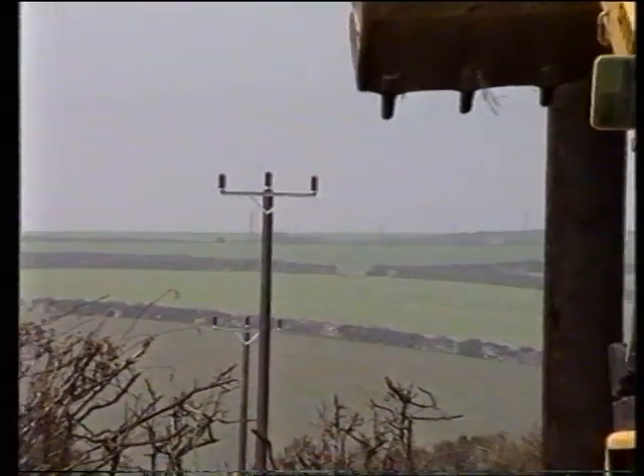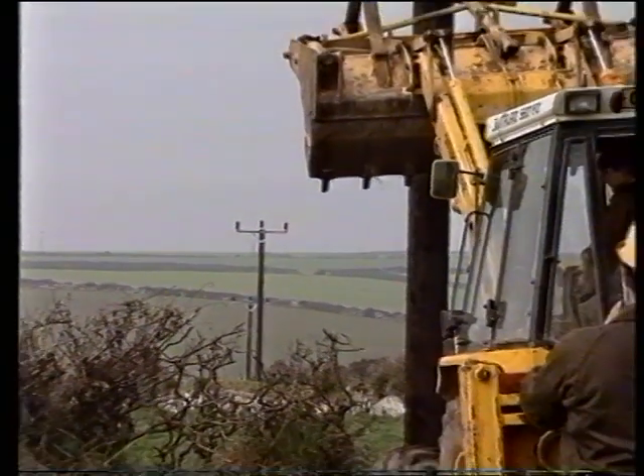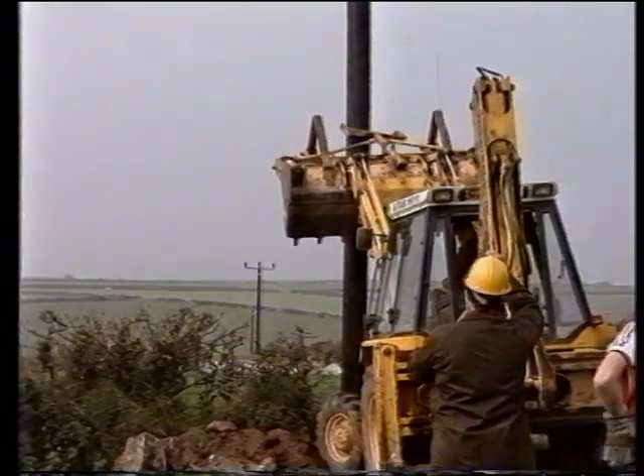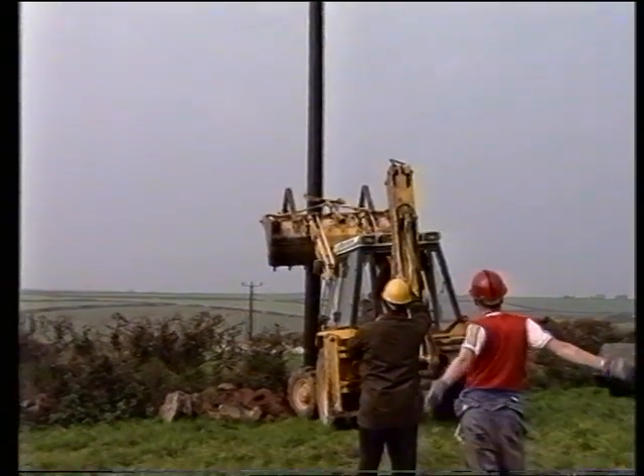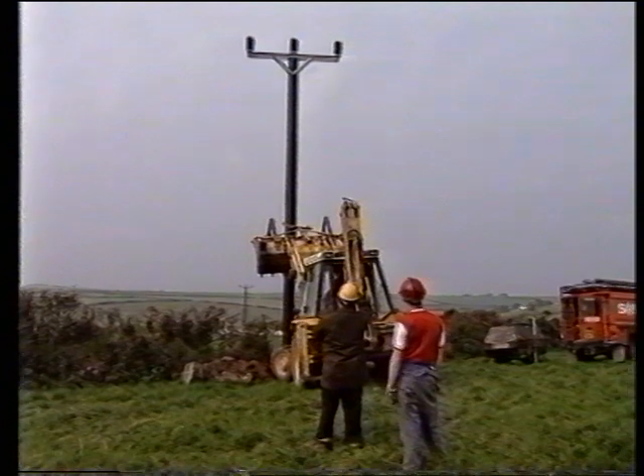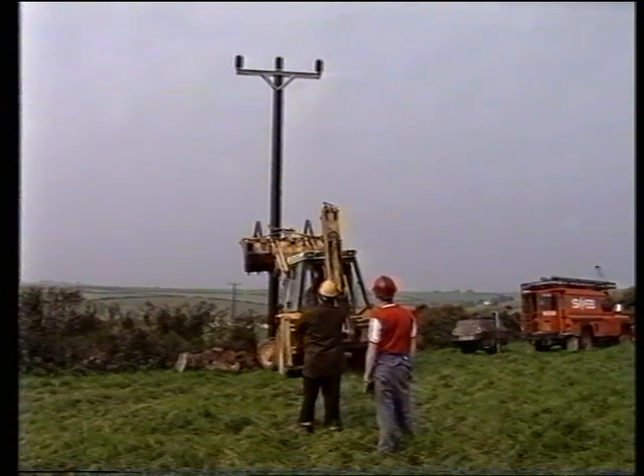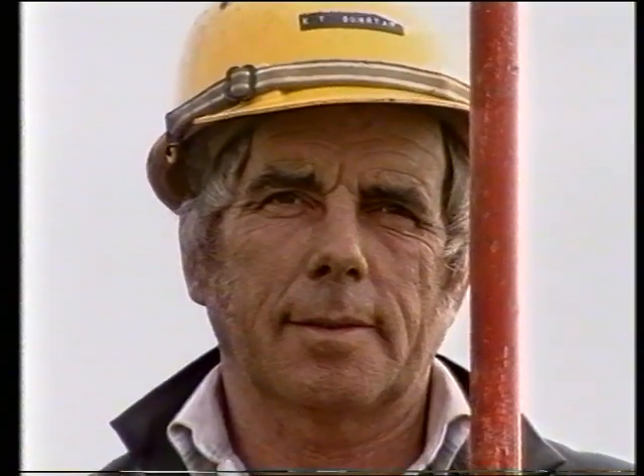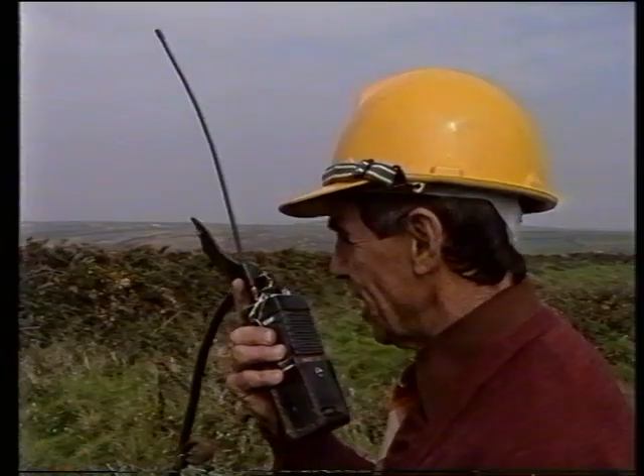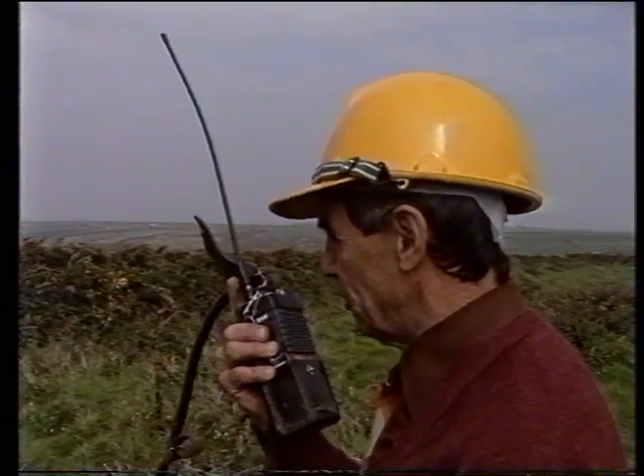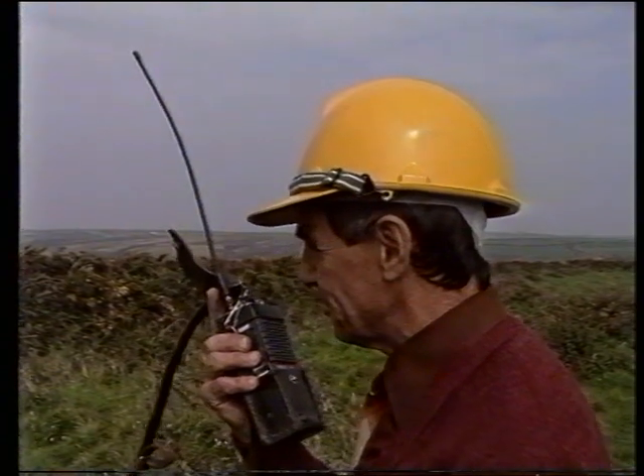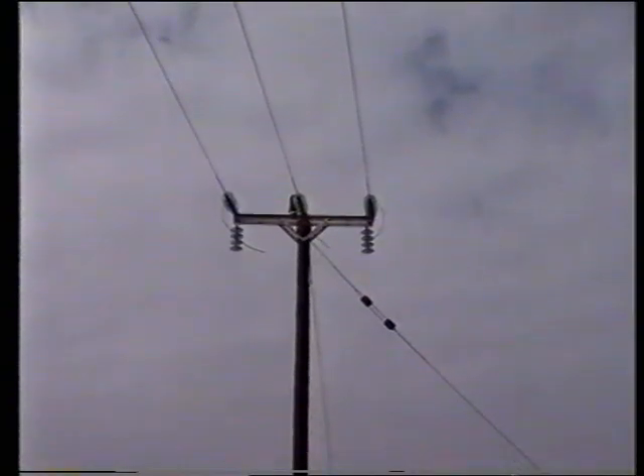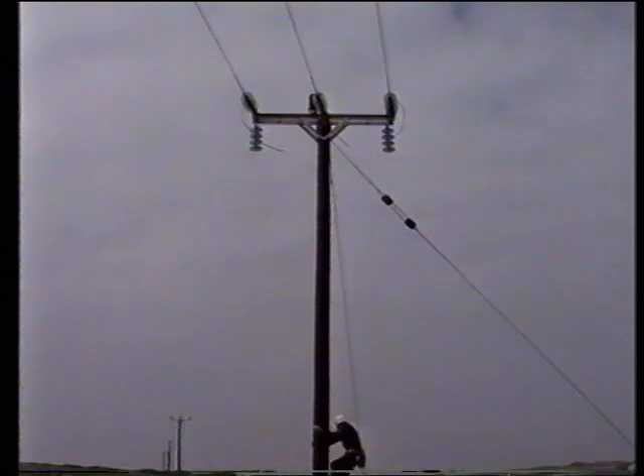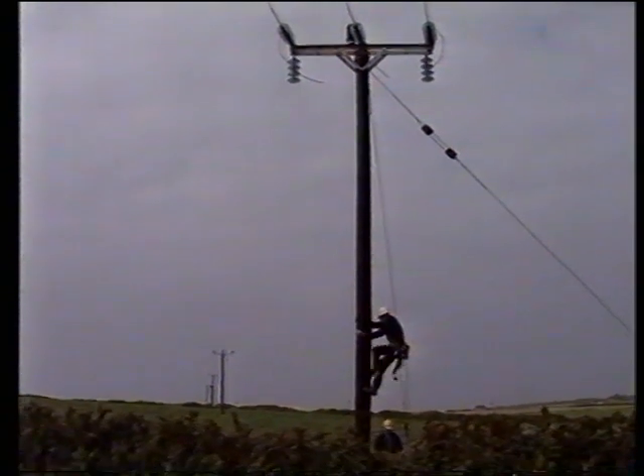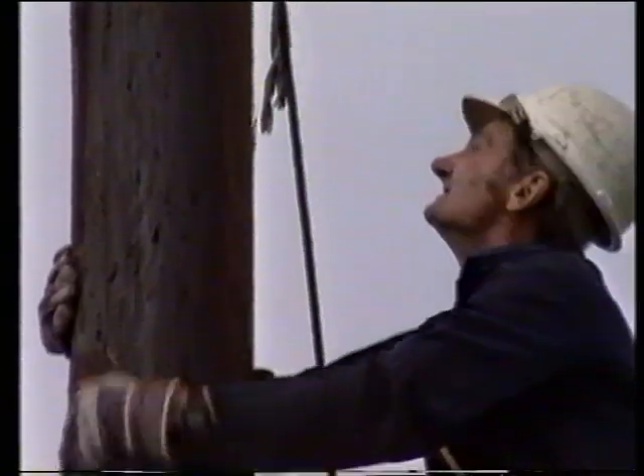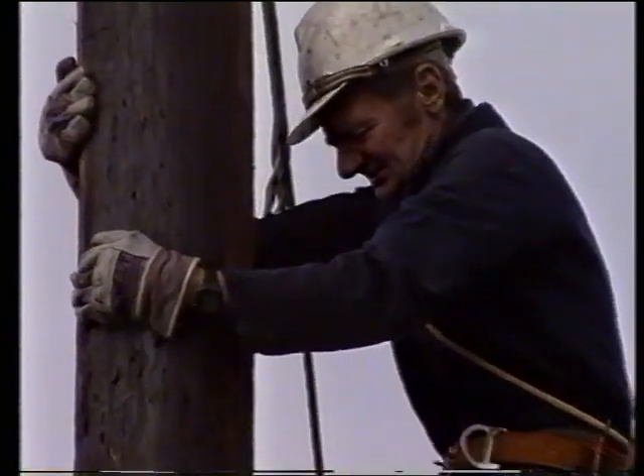It's work that takes several weeks to complete, and as each pole goes up, it's checked to make sure it's vertical, and then it's checked again to see that it's level and in line with the other poles. You can hang up now, and after we've hung up, you pull back and cut the conductors. Over. Now, SWEB's Cornwall linesmen are stringing up the conductors to carry the power, and with their climbers on, they go up each pole in turn to prepare it for the stringing operation.